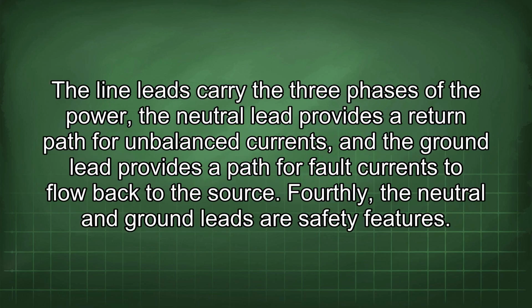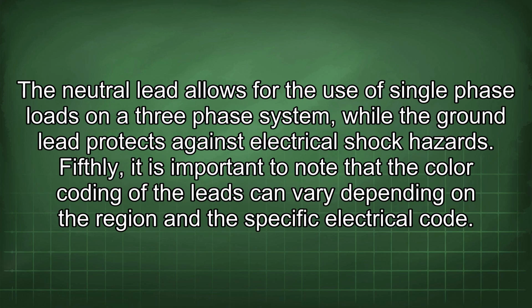The line leads carry the three phases of the power. The neutral lead provides a return path for imbalanced currents, and the ground lead provides a path for fault currents to flow back to the source. Fourthly, the neutral and ground leads are safety features. The neutral lead allows for the use of single-phase loads on a three-phase system, while the ground lead protects against electrical shock hazards.